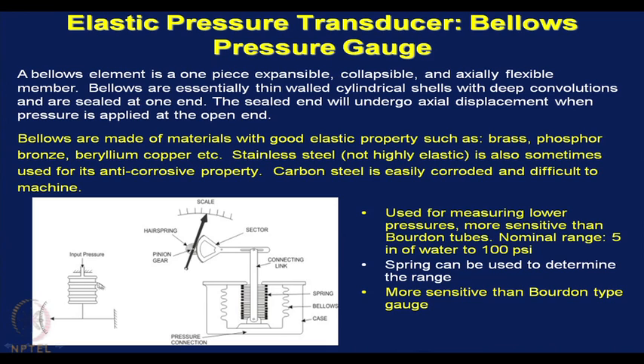So, it is essentially a collapsible member sealed at one end. It has deep convolutions made of thin metallic shells. When I apply pressure at the free end, the sealed end undergoes axial displacement, and that displacement is a measure of the pressure being applied.